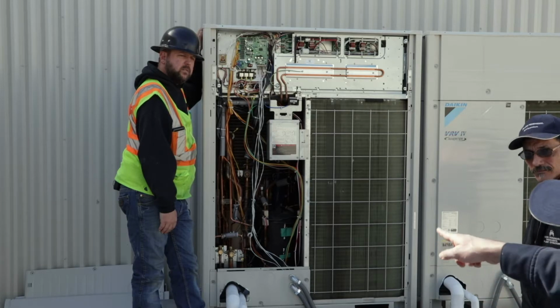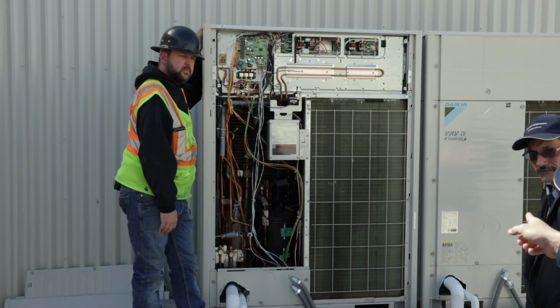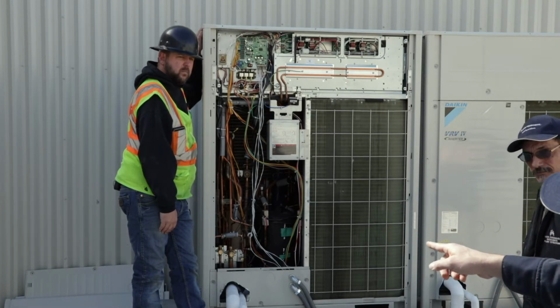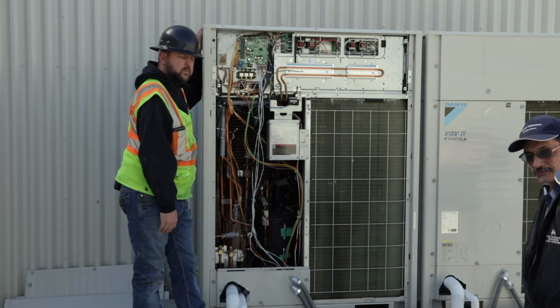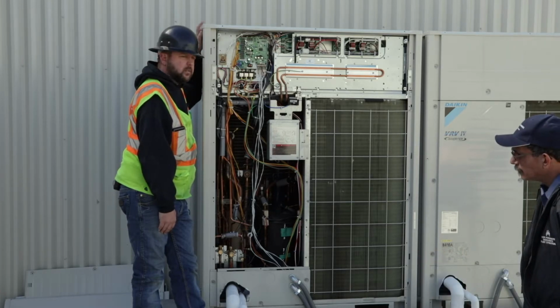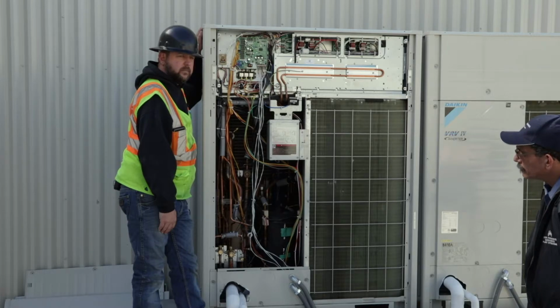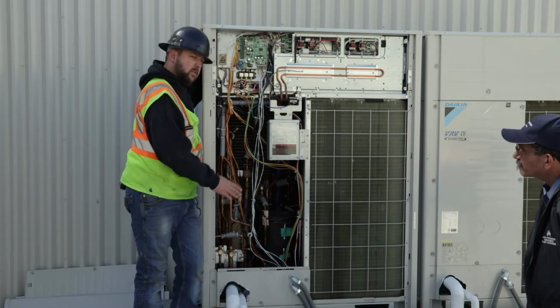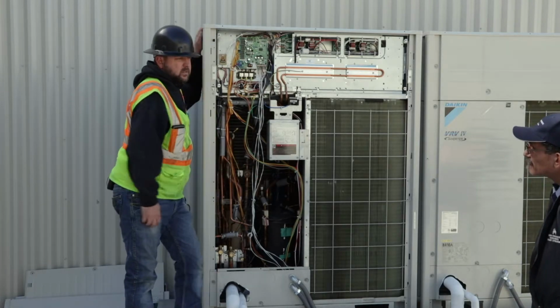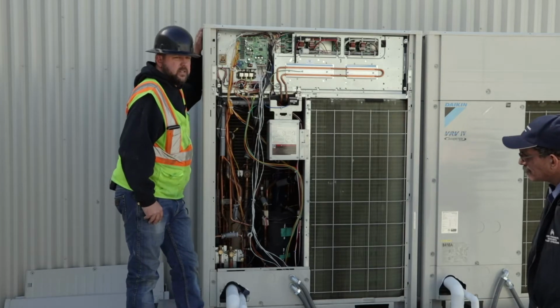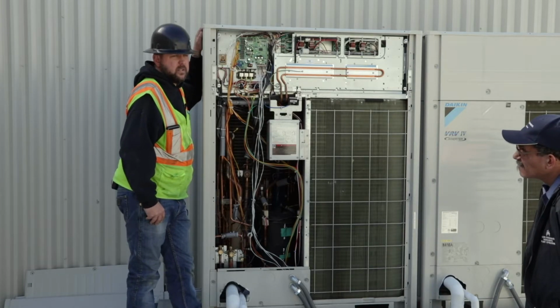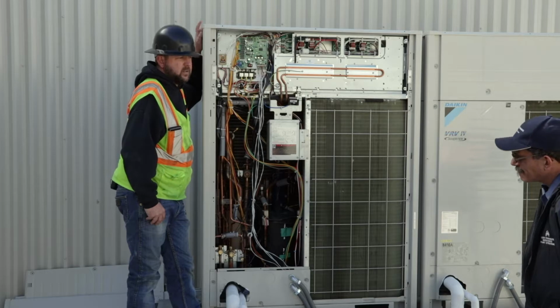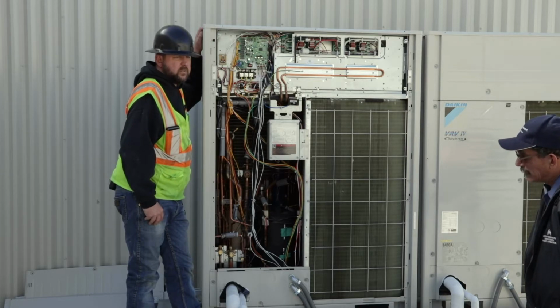If there was a problem with this master unit, we needed to make this the master, like you were saying, is there anything we need to close off the refrigerant to this unit also? No, nope, just let it go, yep. Now, if you have a burnout, that might be a different situation. You're probably taking the whole system down at that point. You're gonna have to clean the whole system. Right.